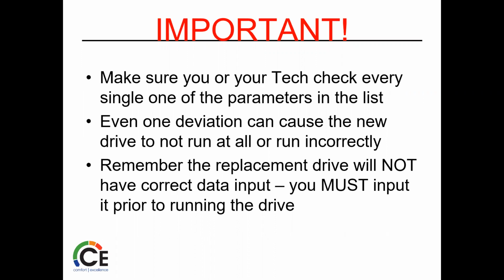So one deviation causes you an issue. And of course, as I said, the replacement drive does not have the correct data. So you are going to have to do it yourself prior to running the drive. We never want the VFD to be on. So we're going to check that, make sure it's off. And we never want the unit to have a call when we're programming this.